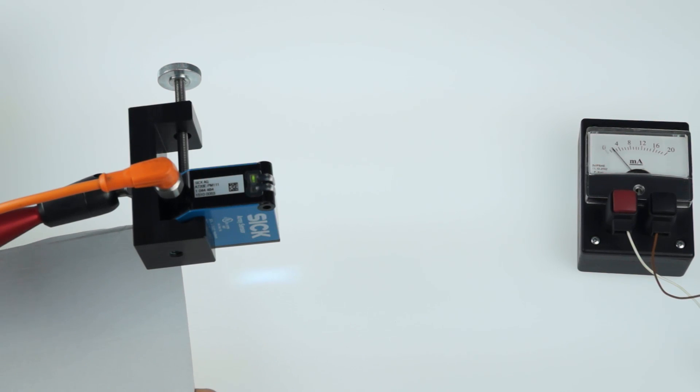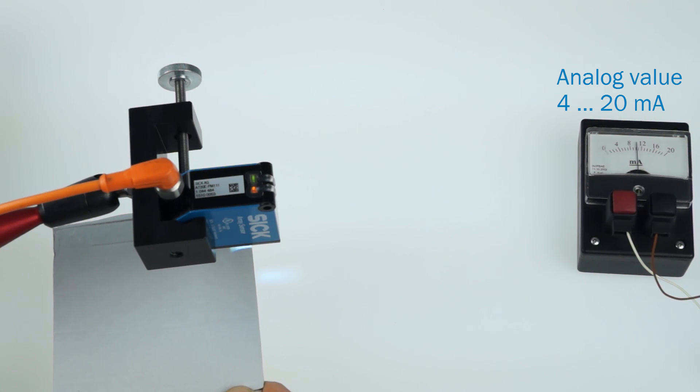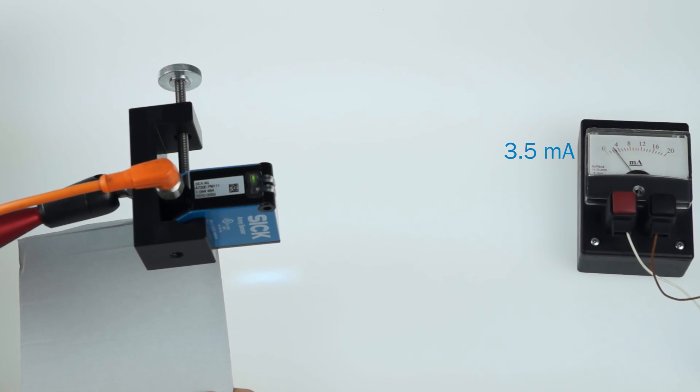The array sensor detects the first edge of an object from the sensor's plug side. Depending on the actual position, the sensor shows an analog value between 4 and 20 mA. If the material leaves the detection area on the plug side, the sensor shows a value of 3.5 mA.